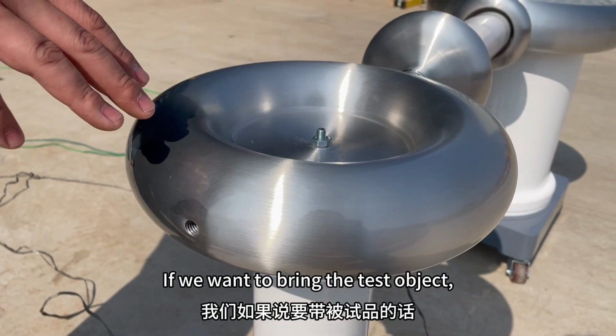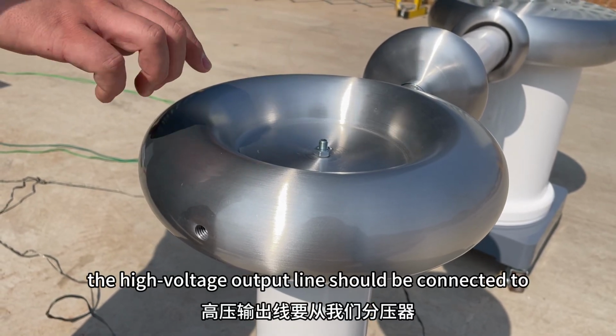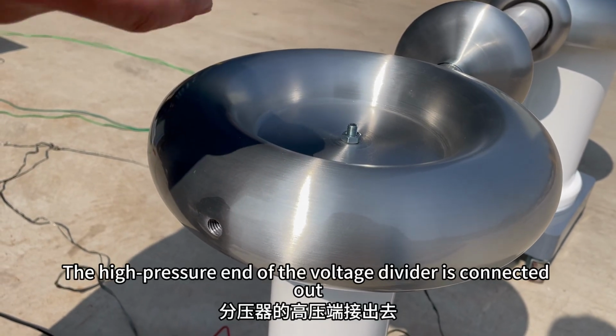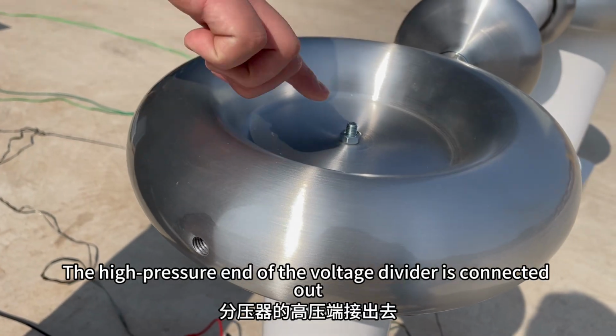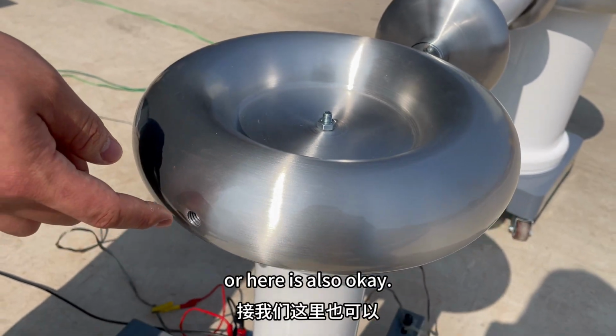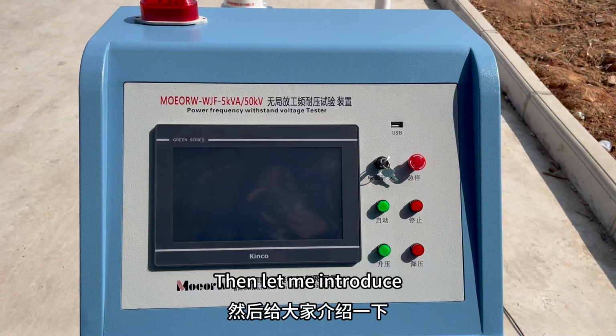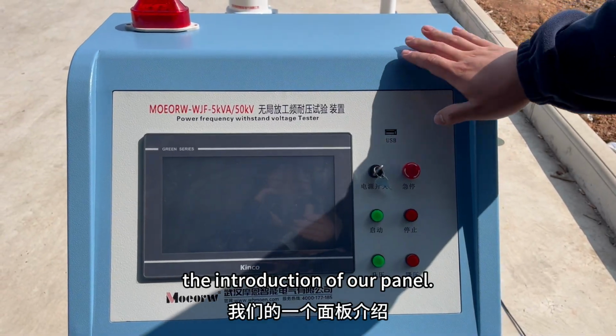If we want to bring the test object, the high voltage output line should be connected to the high voltage end of the voltage divider. It can be connected here, or here is also okay. Then let me introduce our panel.